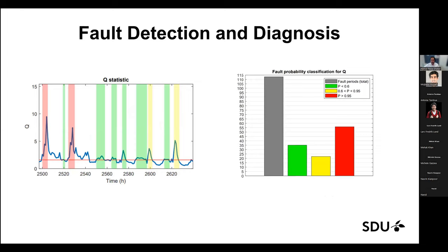The second tool that we developed was fault detection and diagnosis for the distribution network. You have a bunch of variables, readings from the sensors. All of them you put in one matrix and reduce the dimension, and then you define a condition indicator for the network. Now you can see this curve, the Q statistics, and you have a bound. When you deviate from this and go up, there is a violation. And of course, you also filter it like before using the Chernoff bound, and here it is obvious which one is more serious than the others to look into. There is also always a way to go back to the sensor responsible for the problem using contribution plots and things like this.